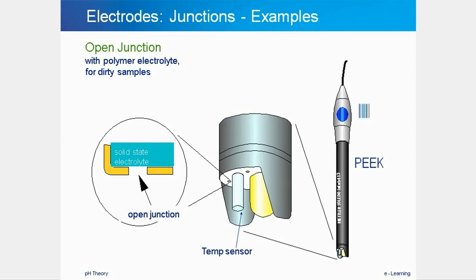A third option is the open junction, which has no barrier between the inside and outside of the reference element. This is only possible if the inside of the electrode contains a solid polymer electrolyte, which controls the flow of electrolyte during measurement so no complete loss of electrolyte takes place. The InLab 430 electrode is shown with its open junction at the bottom next to the glass membrane sensing part. The temperature sensor also sticks out of the bottom right next to the pH membrane. The polymer solid state electrolyte is in direct contact with the solution and exchanges ions to maintain a stable reference potential. This junction is usually used for very dirty samples like soil suspensions.